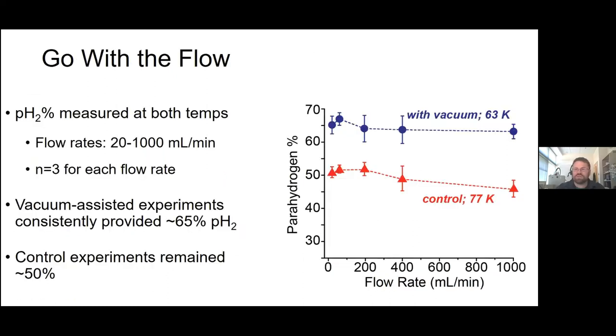We did this at both temperatures, both with the vacuum at 63 Kelvin and also without vacuum at 77 Kelvin. The control is the red line, the colder one is the blue line above it. We did this at different flow rates, from 20 milliliters per minute up to 1000 milliliters per minute. We did each data point three times, so we have an average and standard deviation to report. Under our regular liquid nitrogen temperatures, we get around 50 to 52% parahydrogen. It drops off a little bit as we increase flow rate, but not by very much. When we use the vacuum pump to cool the liquid nitrogen, we can generate higher fractions of parahydrogen upwards of around 65%, and that stayed fairly constant throughout the different flow rates as well.